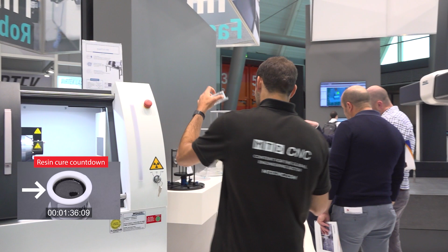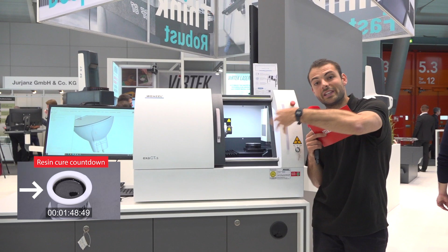scanner here. The reason it's so small, the space is so small, is because these need to be fully protected. This is a fully protected cabinet. If you imagine when you go to a dentist and you get your teeth x-ray scan, the dentist has to go outside and the nurse has to go outside because there's a little bit of an exposure to x-rays every time that happens. So they have to go outside. You only get exposed a little bit. But because this is fully protected, fully lead lined, they can be CT scanning, firing 130 kilovolts worth of x-rays onto a component here while people are walking around. Absolutely fine. So this is a super safe piece of kit that you can use to inspect density, geometrical accuracy. That's computer tomography, but it's really inspection.